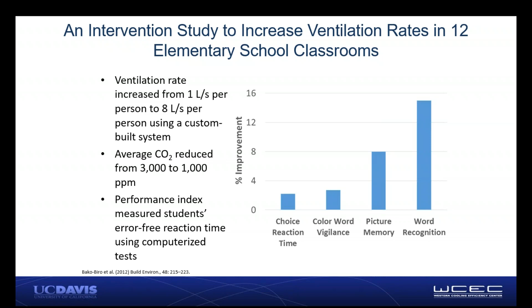This is one example where the researcher increased ventilation from 1 liter per second per person, which is not adequate, to 8, roughly what the ASHRAE standard is. As a result, CO2 decreased from around 3,000 to closer to 1,000. In this case the researcher used a computer test, measuring improvement in word recognition, picture memory, and other tasks. You can see there's a clear improvement in how students performed.